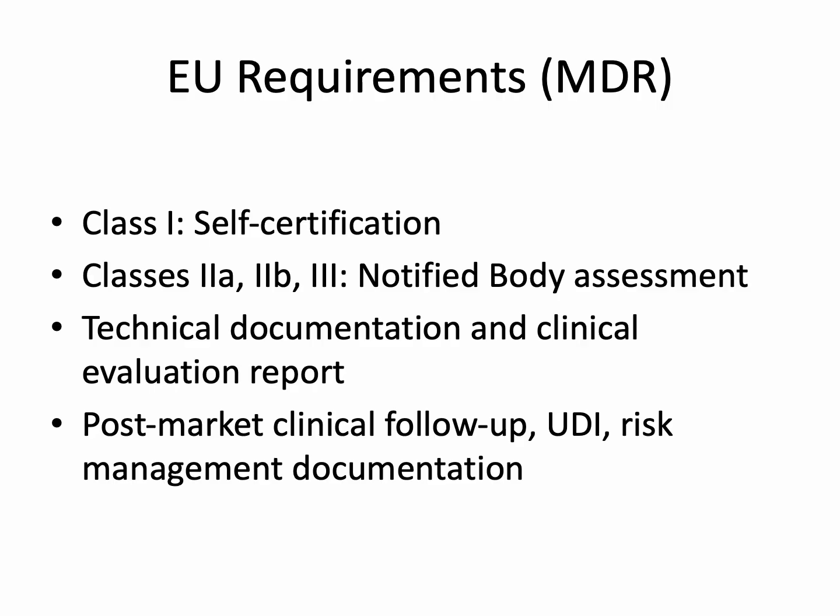Evidence requirements include comprehensive technical documentation, clinical evaluation reports, post-market clinical follow-up, PMCF, unique device identification, UDI, and robust risk management documentation. Compliance with EU MDR standards ensures the device meets stringent safety and performance expectations across European markets.